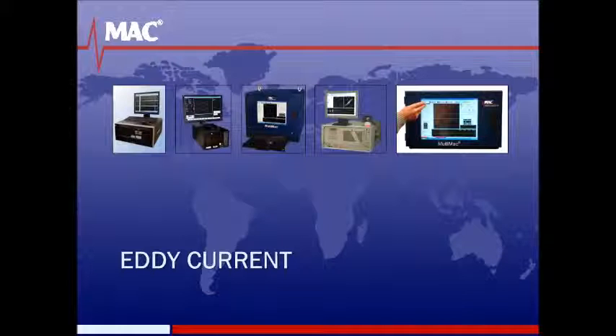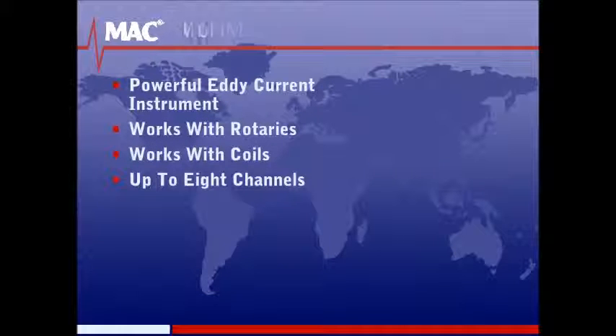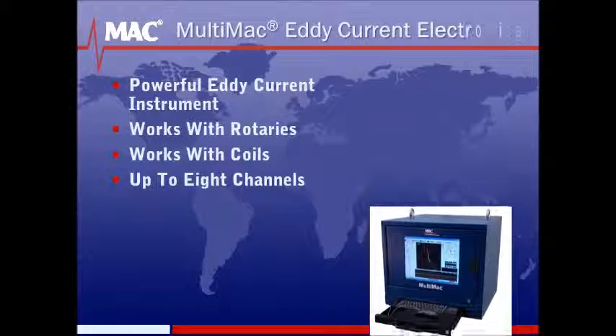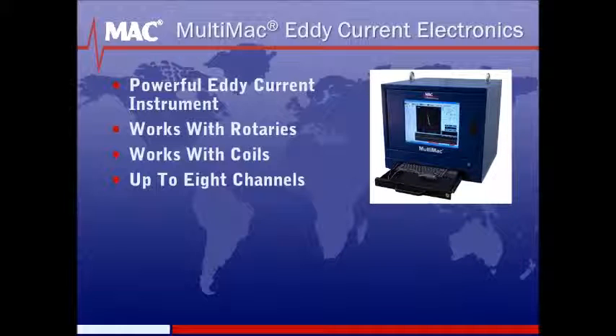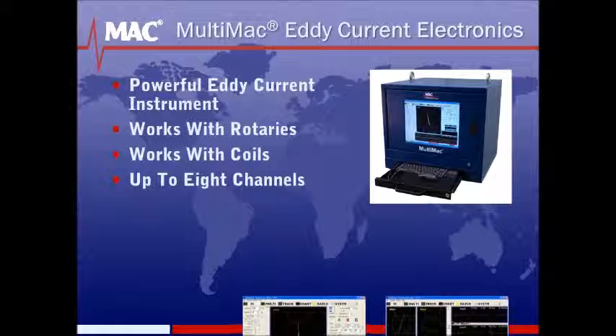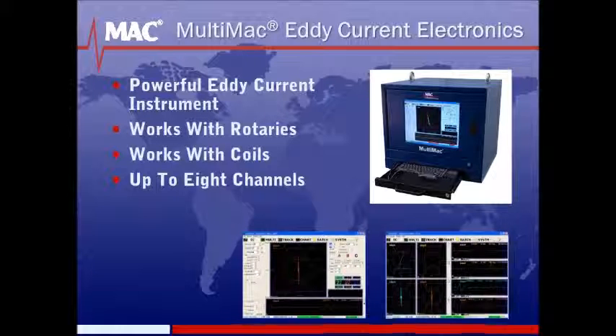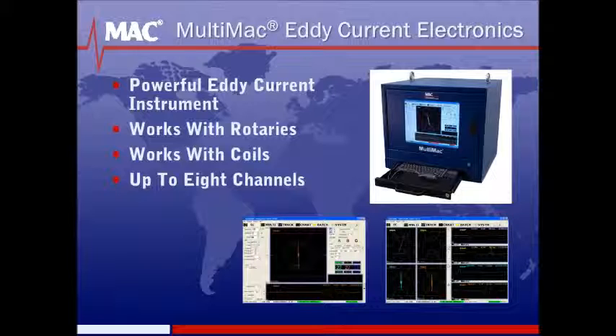MAC has a broad range of eddy current testers and electronics. The Multimac lets you configure your eddy current test application the way you want, all with just one tester. Multimac test channels can be individually configured for use with encircling or sector test coils, as well as rotating test probes, eliminating the need to have several instruments. All test channels can operate simultaneously at the same or at different frequencies. Test speeds can range from 1 foot per minute up to several thousand.